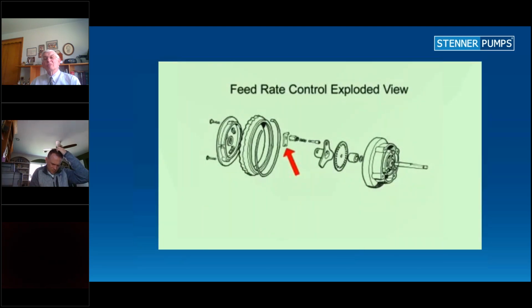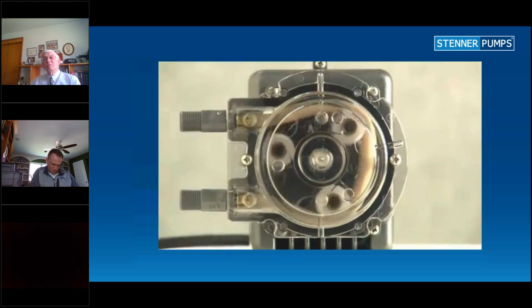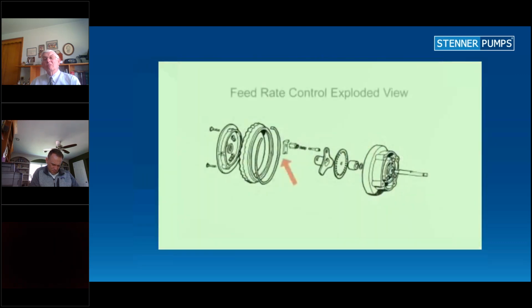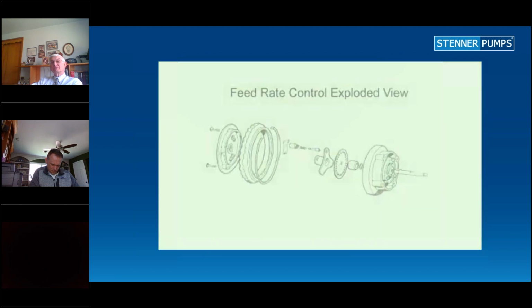When the lifter drops into the feed rate control channel, the pin engages the index plate, which rotates the shaft extending through the roller assembly that squeezes the pump tube to dispense the solution. When the lifter rides on the cam, the pin disengages the index plate and the roller assembly does not rotate, resulting in no pumping action.